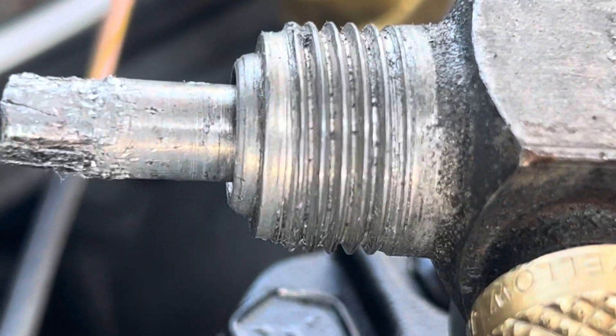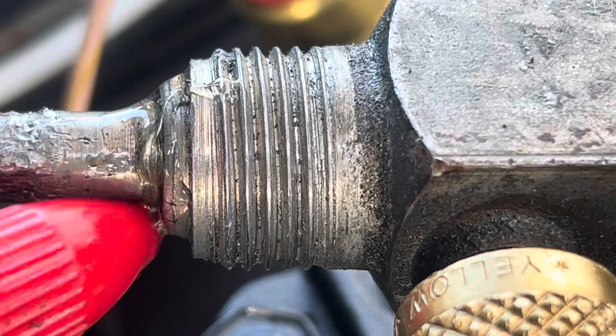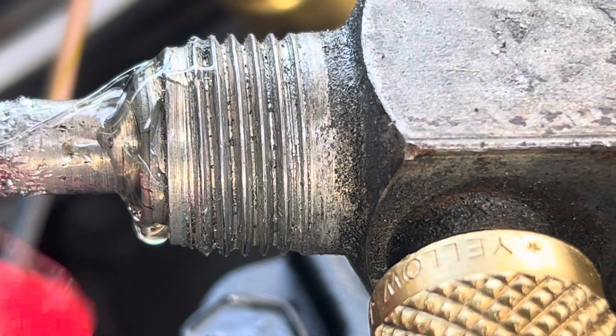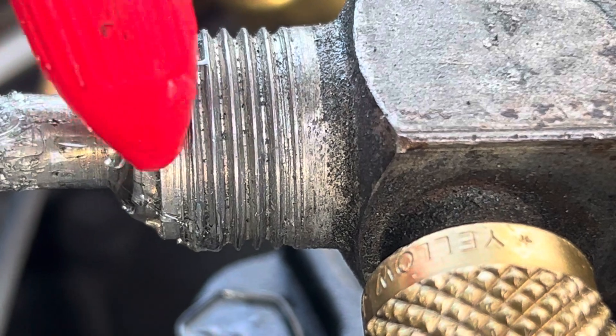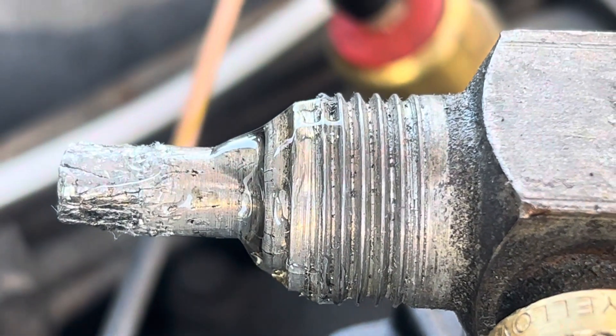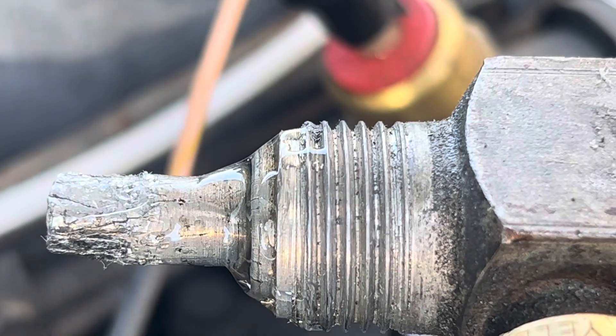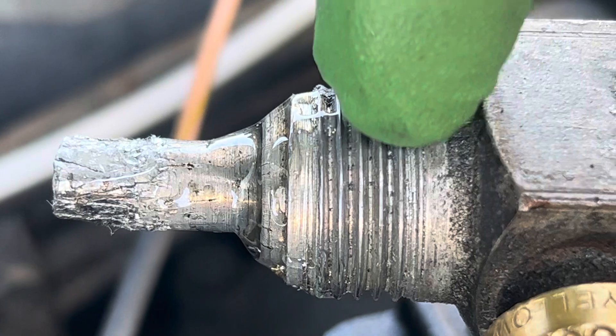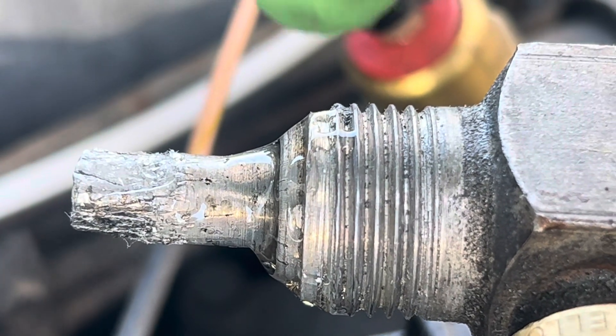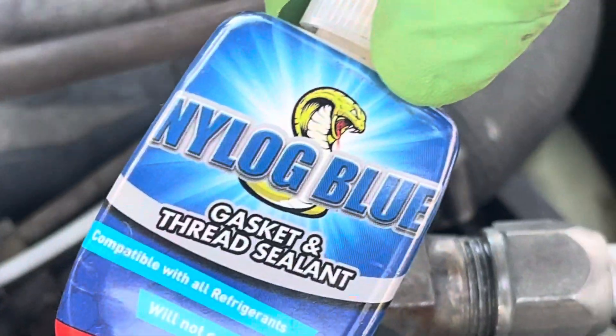Get a little closer — that's more than needed, that's too much, but you can see the leaks right there. Sometimes you'll have a leak and you'll never be able to pull vacuum because of this packing in here leaking.